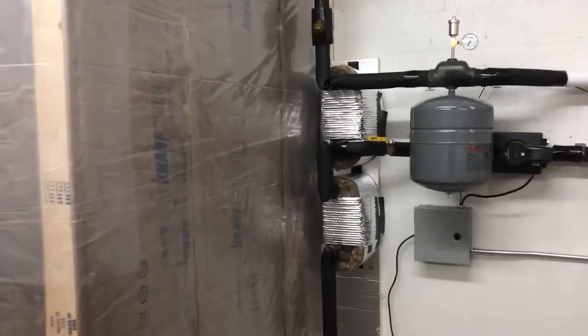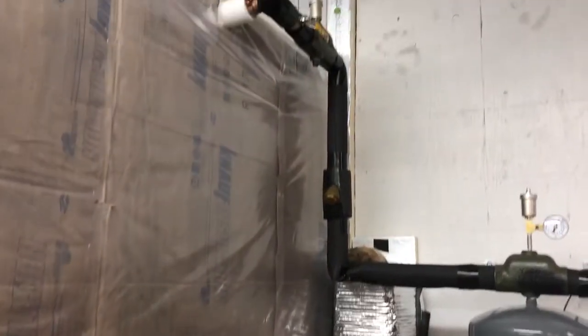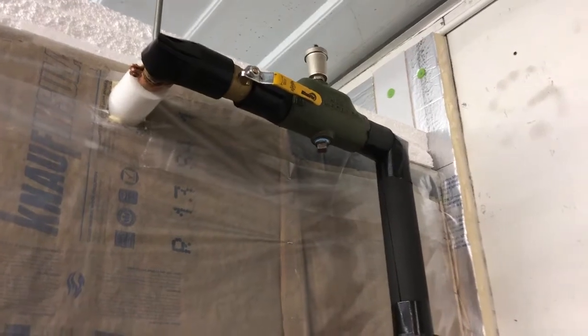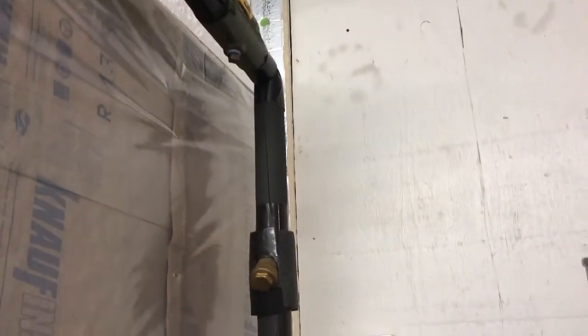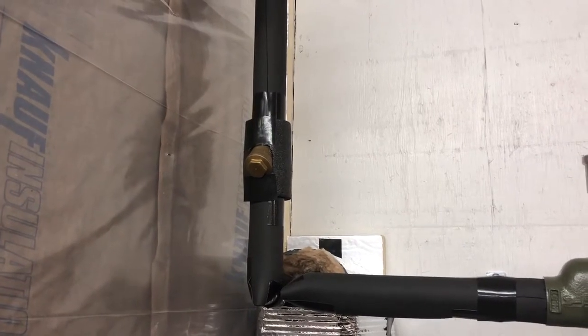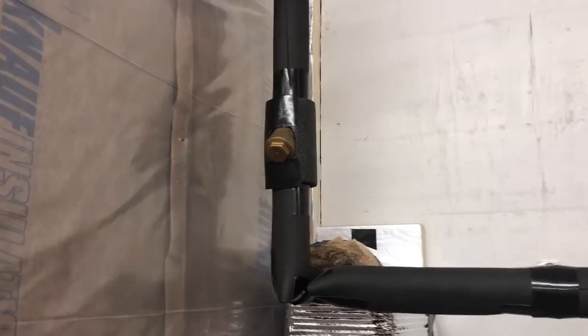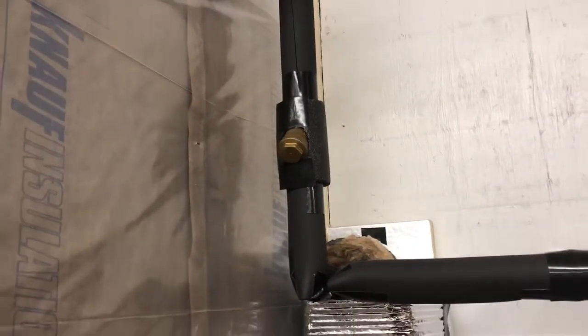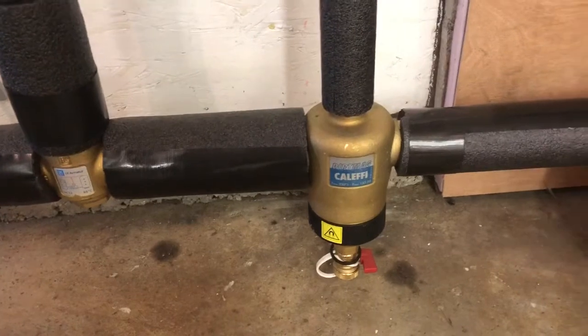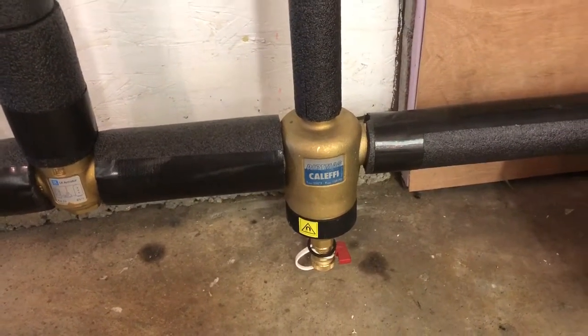We're pulling off hot water off the top of the top tank in thermal storage — isolation valve, Taco air scoop. We're using one-inch copper lines. We have a strainer here to protect the plate exchangers which are next in line. Actually, I don't recommend a strainer; these things can plug up fairly quickly and you've got to open up your system to clean them out. I would really recommend Caleffi dirt traps — very much less likely to plug up and serviceable with the system in use. I'll probably be pulling that strainer out and putting dirt separators in its place.